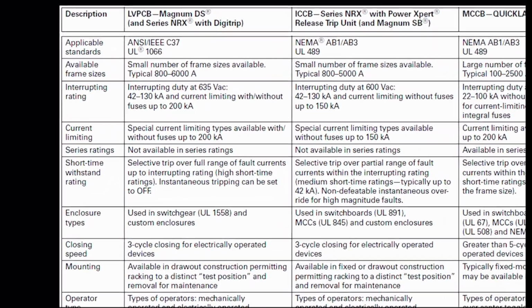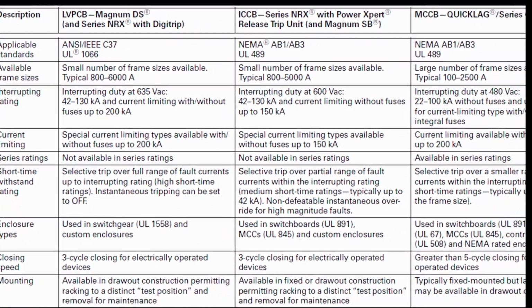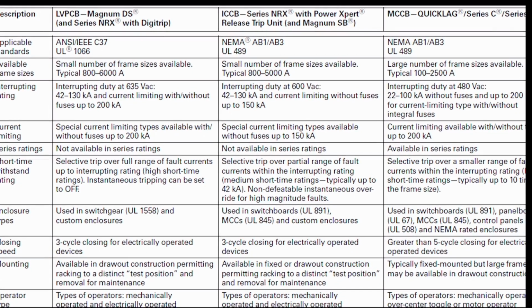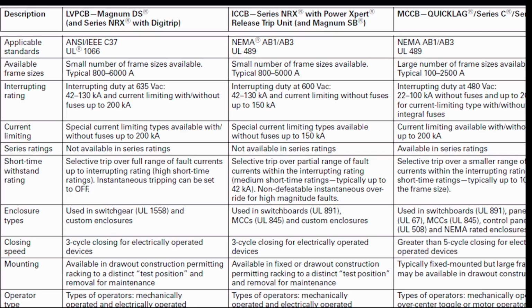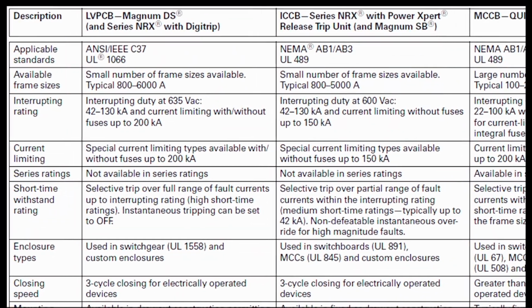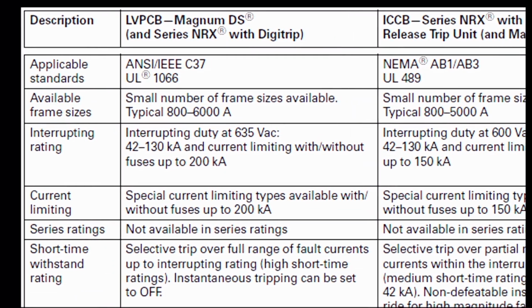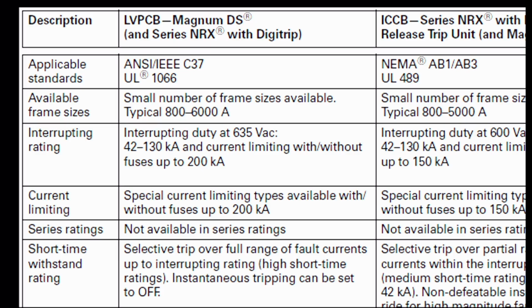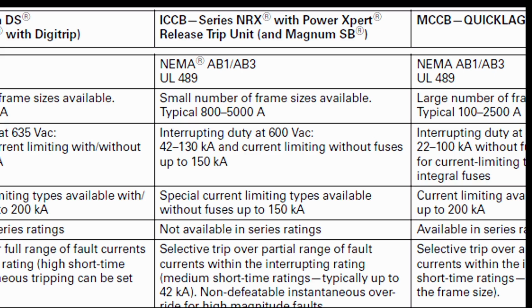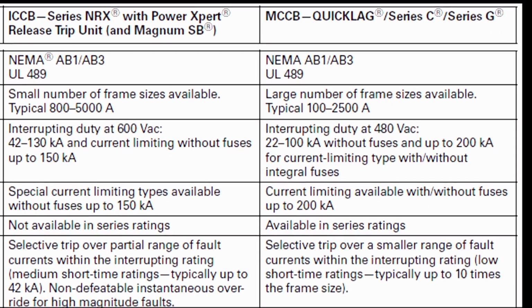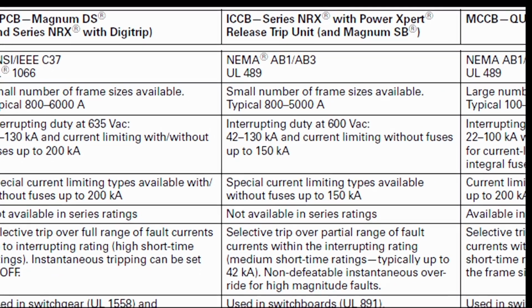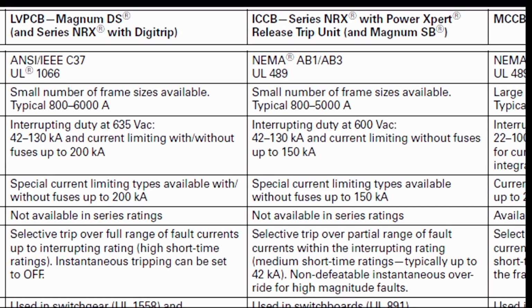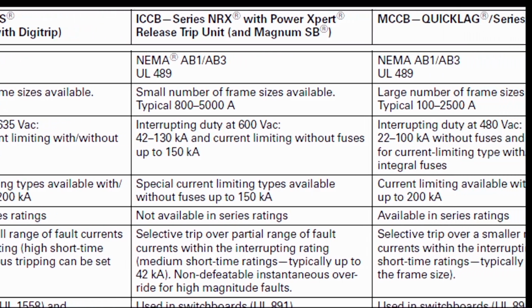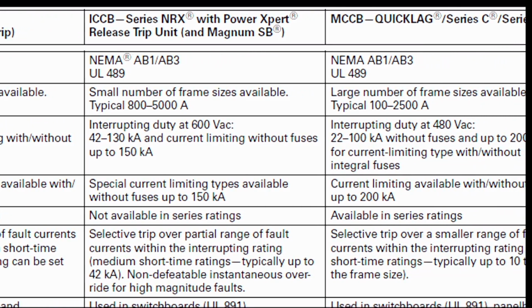This slide here, what I like about this is that it gives you some differentiation. It shows you the column for low voltage power circuit breakers, which is this first column here. This tells you it's ANSI IEEE C37, UL 1066. Insulated case circuit breakers, UL 489. Molded case circuit breakers, UL 489. This also gives you the range: a low voltage power circuit breaker is anywhere from 800 amps to 6,000 amps. An insulated case, 800 amps to 5,000 amps.